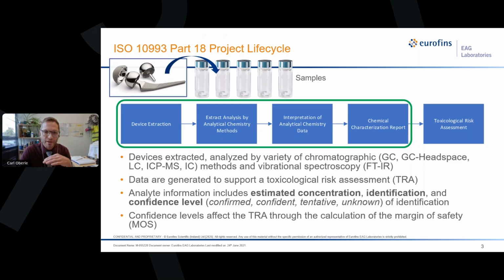At which point, after all that data has been collected and interpreted, it goes into a chemical characterization report, which is then, this is kind of when it leaves our door or the testing facility's door, it heads to the toxicologist for a toxicological risk assessment, or sometimes you see it as a TRA. And the information that's provided to them in the report from the testing facility includes estimated concentration of the analytes detected, identification, and confidence level assignment. And that feeds into what the TRA or the toxicologist will use to generate a margin of safety.